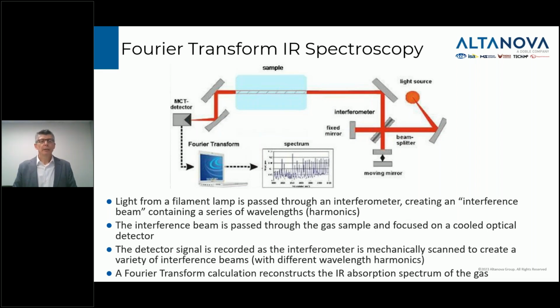The big difference here, though, is the nature of the light source, which is not just a white polychromatic light source, and it's not a narrow light source. It's a tunable light source, and it's tuned using a system called an interferometer. What an interferometer generates is a beam of light that contains a harmonic series of wavelengths. So for any position of the interferometer, we're shining a harmonic series of wavelengths of light through the sample, and the signals are being recorded by this light detector at the other end. And then the interferometer is tuned to scan a whole range of central wavelengths and build up a whole bunch of data with different interferometer settings.